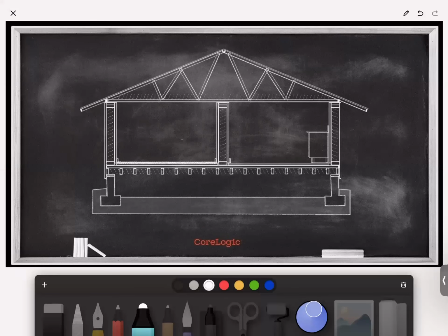Here's the mistake that we make with psychrometrics most commonly in our industry. The most common mistake that we make is we walk in as a technician, so I'll draw my technician here, and my technician has an instrument in their hand, and they take a temperature and a humidity reading with that instrument while they're standing in the middle of the room. The air that we just measured is the air right here. That's the air we just measured. That's what we document. That's what we record into our readings on our documentation. And because that's what we've recorded into our documentation, that's all that gets considered.